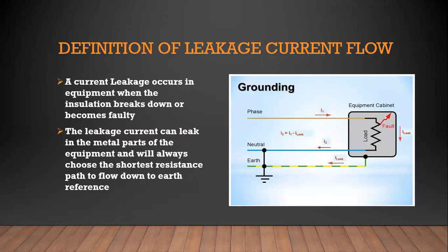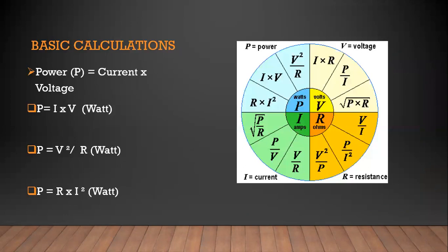Definition of leakage current flow. You'll often get to a site where the client says the earth leakage is tripping, and the geyser is obviously the cause, and that comes down to leakage current flow inside the geyser element. And in this course, I also explain how it occurs, what the definition of leakage current flow is, and obviously then the shortest route path flow down to earth. So that's basically on the leakage current flow.